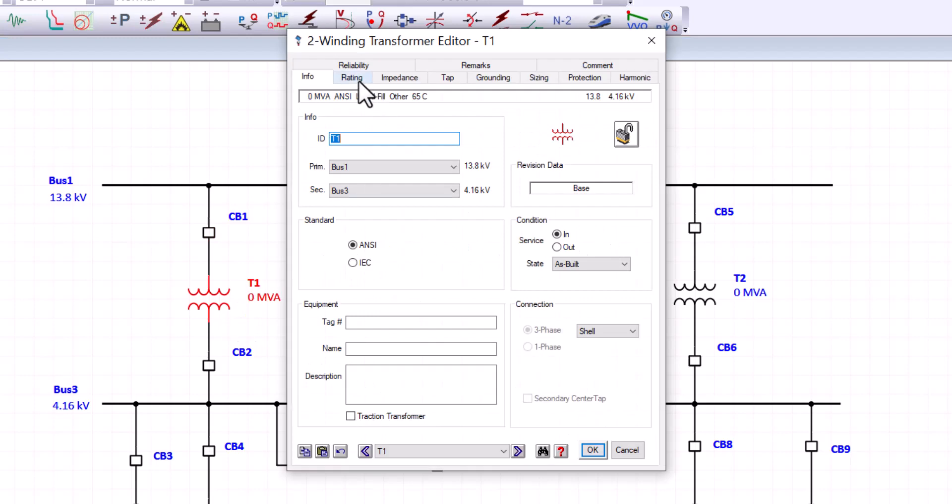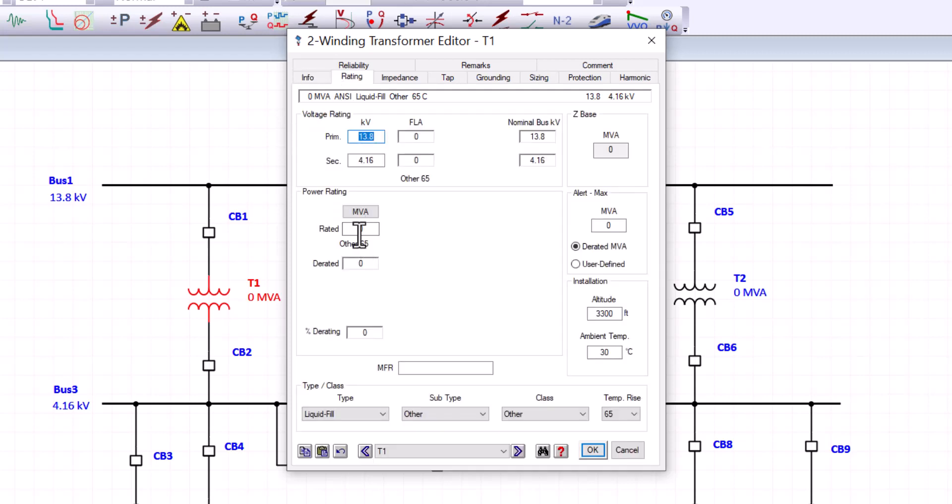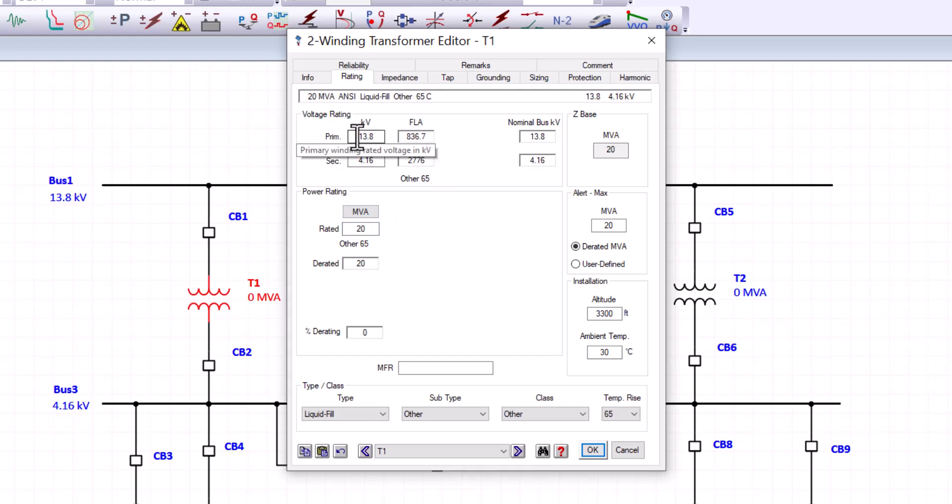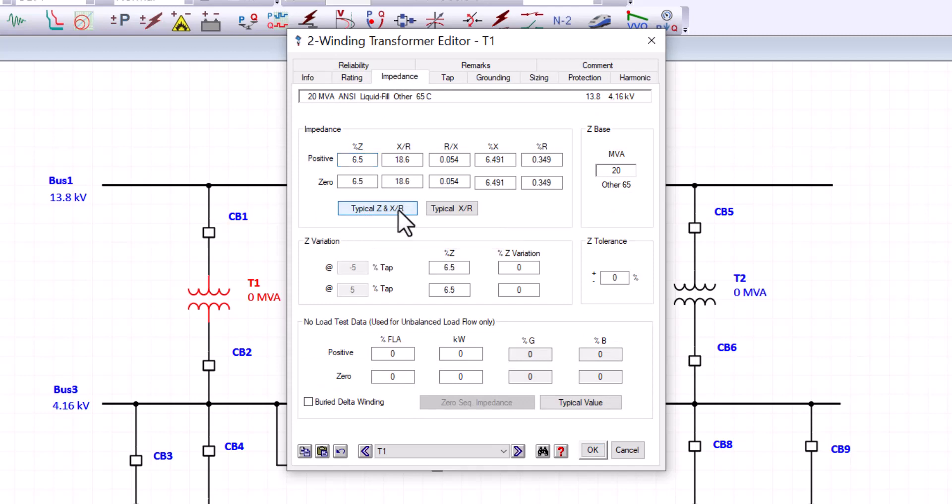The two winding transformer, we can see here, this is just some basic information for the two winding transformer. But the rating tab, we need to put 20 MVA for the power rating. And we checked the primary and the secondary. Yes, 13.8 and 4.16 is what we need to model. Next, we check the impedance. And the typical Z and X over R values will be used. So we'll check that.